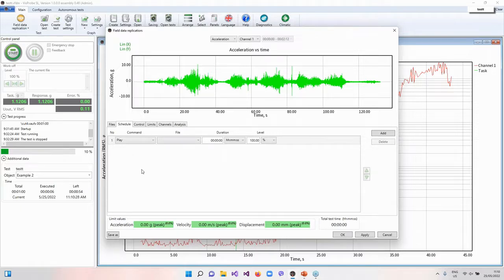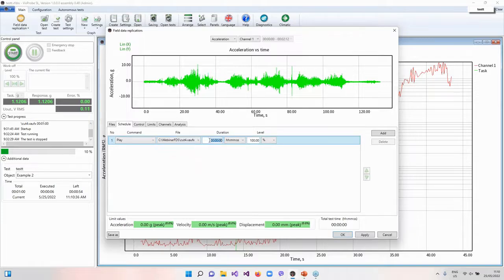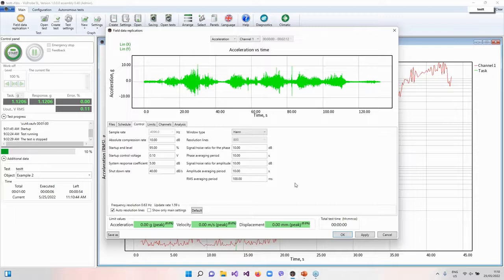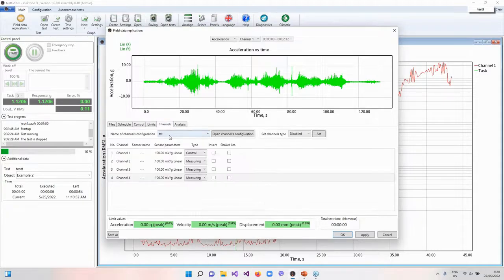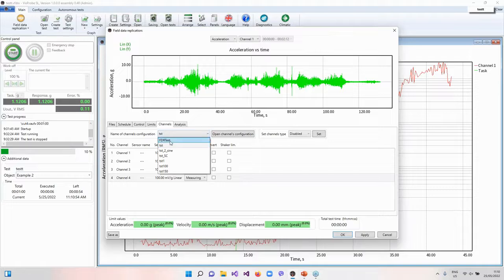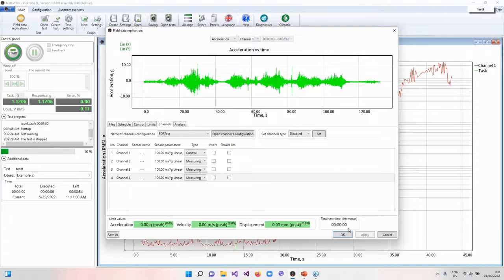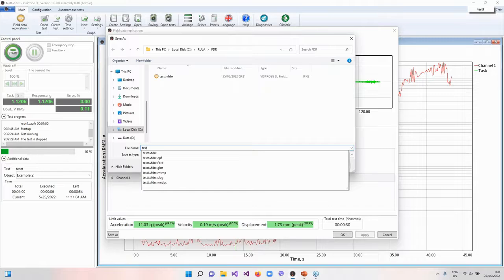After that we go to schedule. The main command for field data replication test is called play. Let's select our file and set a duration to, for example, 30 seconds. After that we go to control, check the settings. In the limits we see that our shaker is selected. And in the channels we will select a pre-created field data replication test configuration. Then we are ready to start the test. Let's save it.